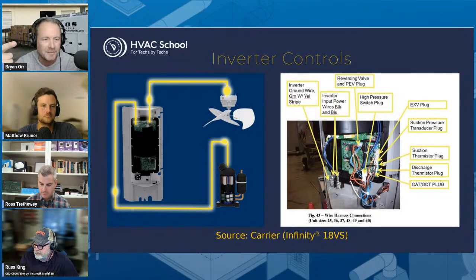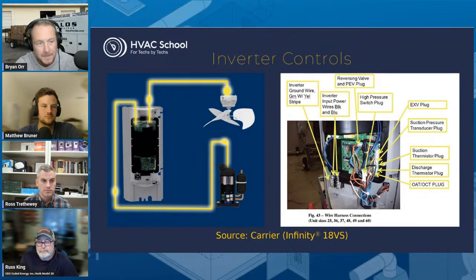But the consequence is that you're not getting that for free, right? They still can provide capacity, but they're doing it by running the compressor at a higher RPM when you're talking about a variable speed compressor, and that is using more power. It's just giving you the ability to still do that with compression refrigeration versus having to use something a little bit more objectionable, like electric heat or potentially even fossil fuels. So that's one huge thing. Any thoughts on that as far as what you've seen? Anybody here, including Matt? No. Okay, this is what I do. Sometimes I get techie nerdy and then nobody wants to say anything. Okay, so I'll keep going.